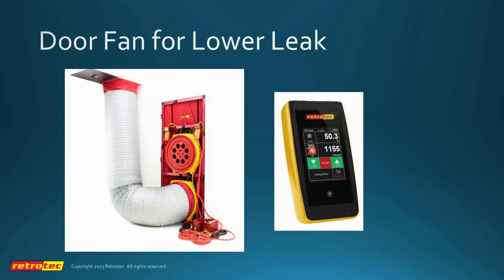Now, the other mistake that people make when they're running the software is they'll measure the lower leaks and put that in as the total leaks, and that's a big no-no. I believe our training emphasizes that point. So the procedure is we first of all measure the total leaks and see if it passes, yes or no. Then once we've measured the lower leaks, we measure the leak fraction and see whether it passes.